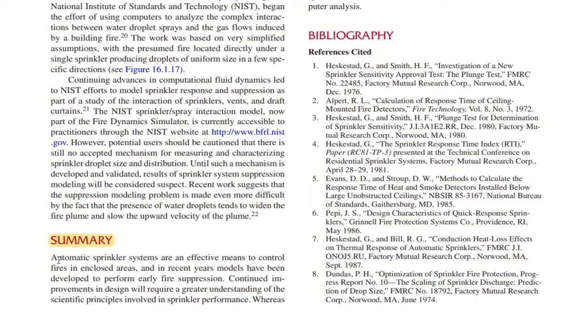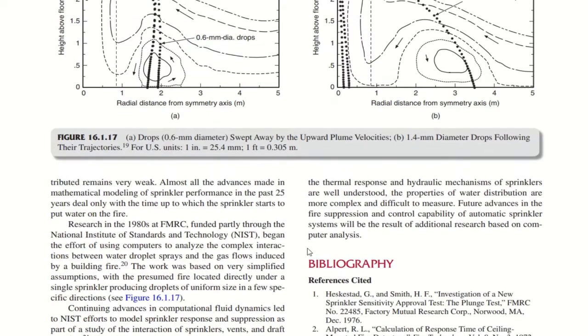In the summary they have mentioned automatic sprinkler systems are an effective means to control fires in enclosed areas, and in recent years models have been developed to perform early fire suppression. So that's why we have early fire suppression sprinklers as well. Continued improvements in design will require a greater understanding of the scientific principles involved in sprinkler performance, whereas the thermal response and hydraulic mechanism of sprinklers are well understood. The properties of water distribution are more complex and difficult to measure. Future advances in the fire suppression and control capability of automatic sprinkler systems will be the result of additional research based on computer analysis.